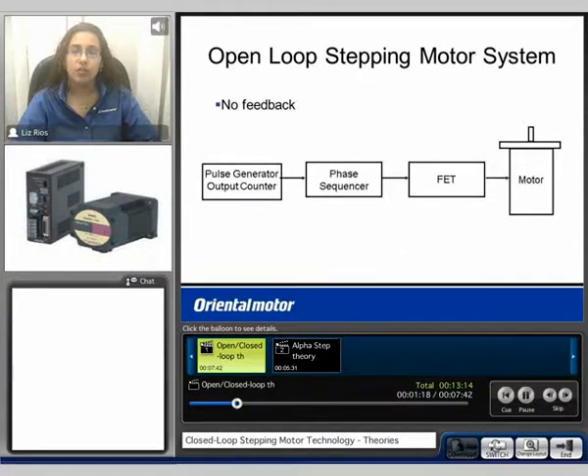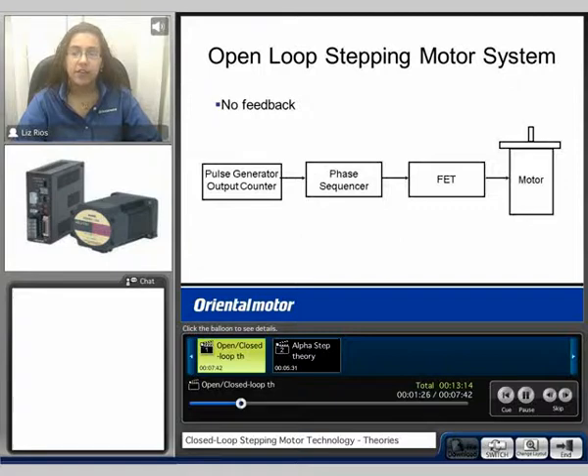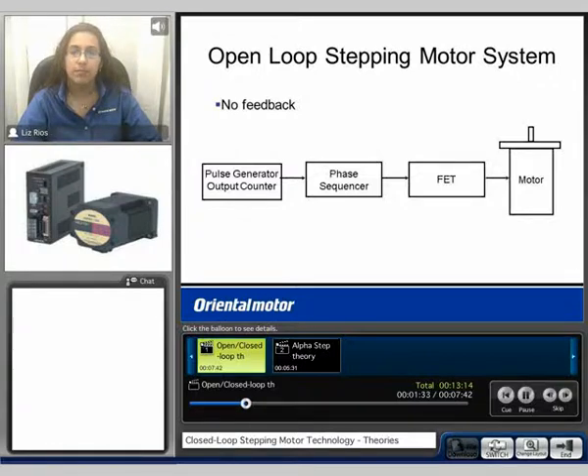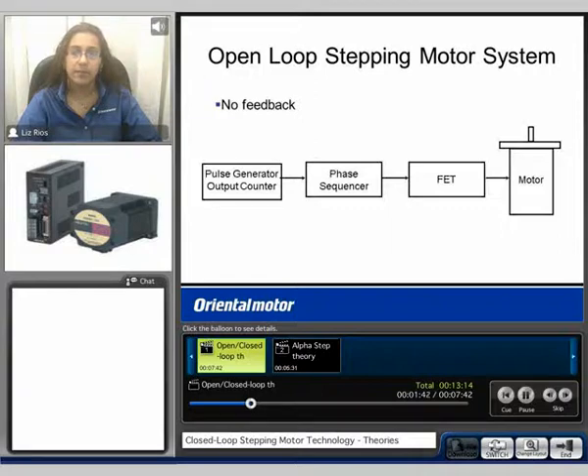Here we can see an open loop stepping motor system. It consists of the pulse generator, which sends pulses to the phase sequencer. The phase sequencer determines which phase is on or off, and the FET energizes the motor phase excitation, and the motor begins to rotate. With an open loop system, there is no feedback, therefore the user doesn't know if the motor has made its commanded move.